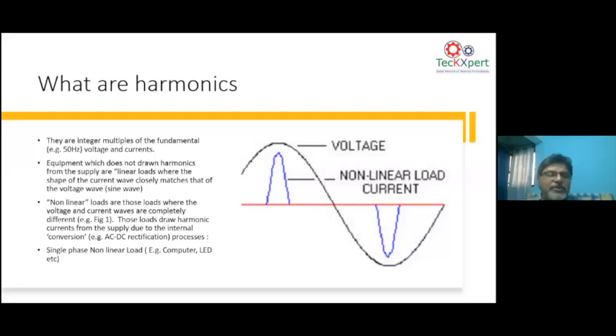But a non-linear load does not work like a normal linear load. For example, when you apply a voltage to a diode, which is a non-linear load, let's say we have a rectifier, and the input side of the rectifier is given an AC input, and the rectifier output will have a DC battery storage, because ultimately in a variable frequency drive or in an SMPS, which is used for LED or any of these applications, you will have a rectifier and an inverter circuit. The rectifier circuit will be primarily diodes. So what happens is this diode will conduct when the voltage goes to its peak. When the voltage is at its peak, like here, the diode will start conducting.